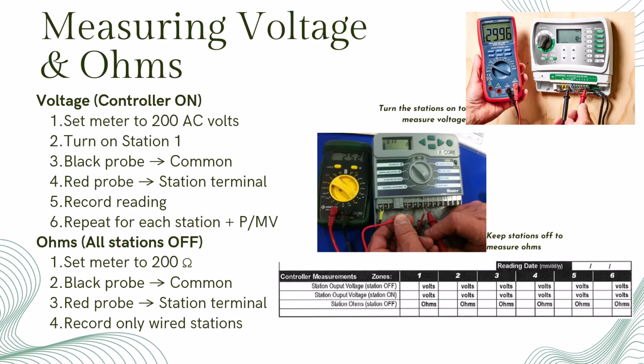To measure voltage, set the multimeter to 200 AC volts and turn on station 1. Put the black probe on the common terminal and the red probe on the station terminal, then record the reading. Move the red probe through each station and the pump master valve terminal. Only the active station and the PMV should show voltage. Then repeat the process by turning on each station one at a time. For ohms, turn all stations off and switch the meter to 200 ohms. Again, black probe on the common, red on each wired station terminal, and record the readings. There's no reason to test empty terminals. Once everything is recorded on the checklist, you now have a complete electrical snapshot of the controller.